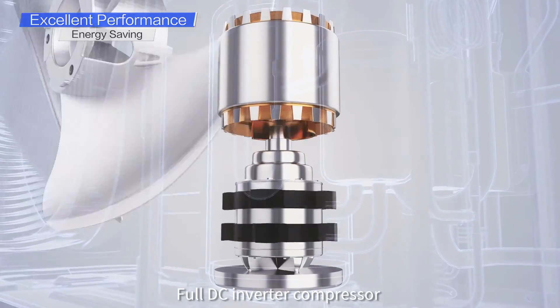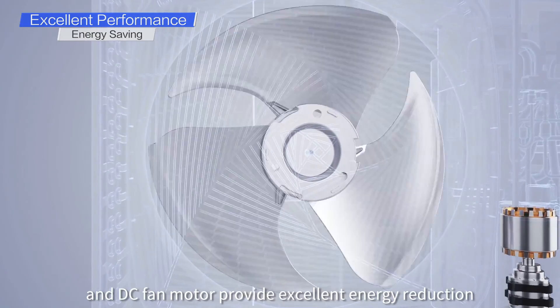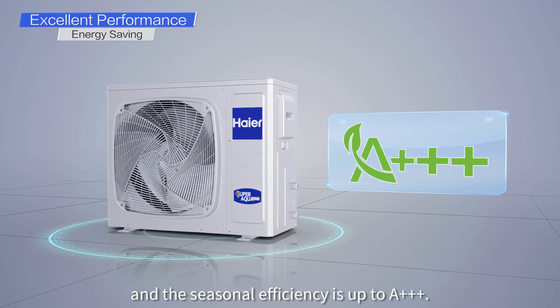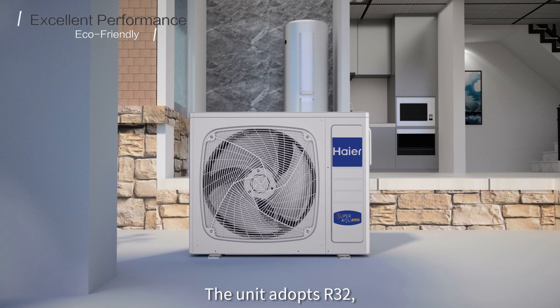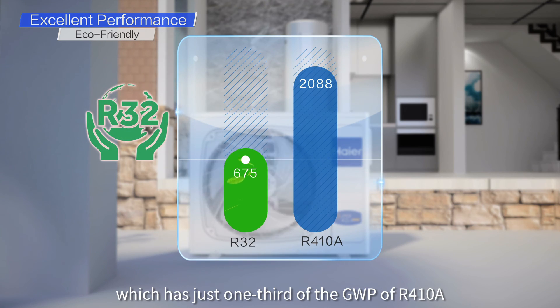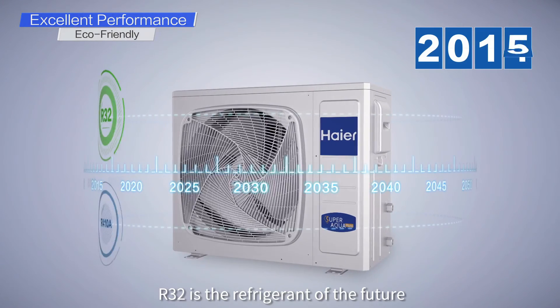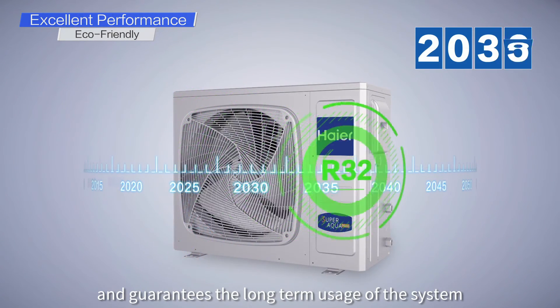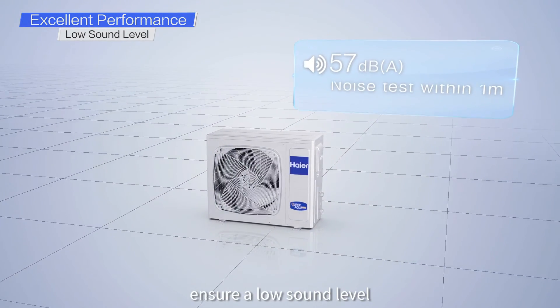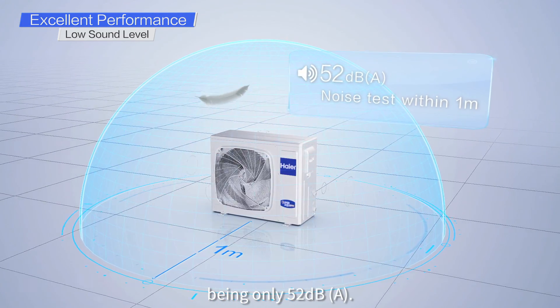The full DC inverter compressor and DC fan motor provide excellent energy efficiency, and the seasonal efficiency is up to A+++. The unit adopts R32 refrigerant, which has just one-third of the GWP of R410A, making it the refrigerant of the future and guaranteeing the long-term usage of the system. Multiple noise reduction measures ensure a low sound level, with the 5 kW unit's sound level being only 52 decibels A.